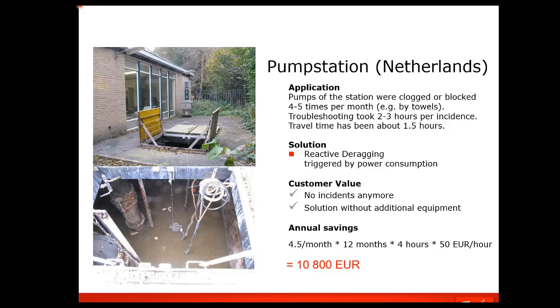This feature has been used, like I said, in other parts of the world. This particular one is a pumping station in the Netherlands. It had a station that was being clogged or blocked 4 to 5 times per month by towels. Every time it happened, they had to troubleshoot it and travel out there about an hour and a half to get there. Using the derag feature has actually cleared this up for this particular station, and they have had no more incidents just using the reactive part of it, based on the power tuning. So anytime a towel came in, it would derag itself and clear it up and then send it on its way. So this particular site has seen a major cost savings just using that feature, based on travel time and pulling the pump and all that stuff of clearing it.